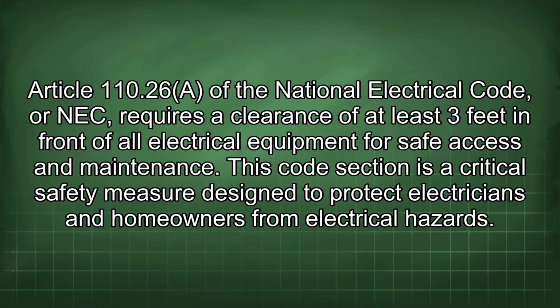Article 110.26 of the National Electrical Code, or NEC, requires a clearance of at least 3 feet in front of all electrical equipment for safe access and maintenance. This code section is a critical safety measure designed to protect electricians and homeowners from electrical hazards.